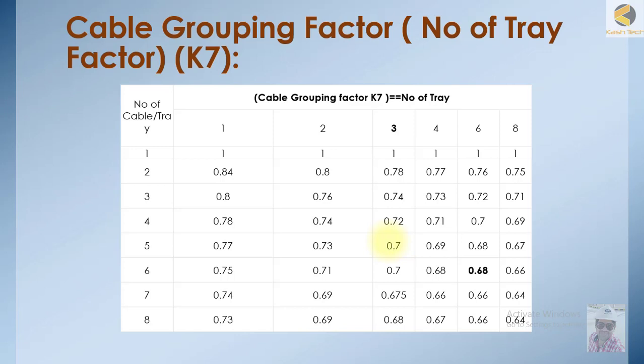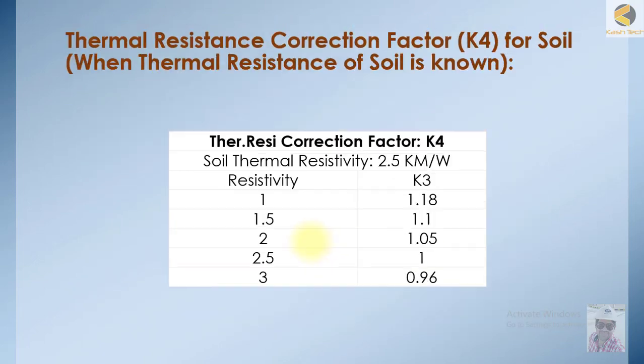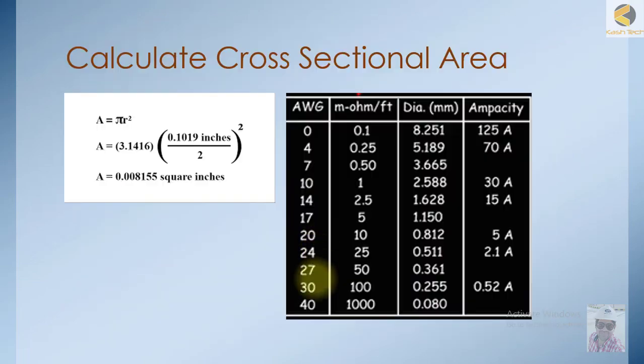Then we have the cable grouping factor K7, which refers to how many cables are grouped together in a tray. I have covered the theoretical part explaining how this factor is decided. If there is only one cable in a tray, the derating factor is 1 — there is no derating. As you keep increasing the number of cables within the tray, the rating of the cable comes down. The reason is that other cables are already producing a heating effect, increasing the base temperature of the cable, which reduces its rating. These are basically the correction factors.